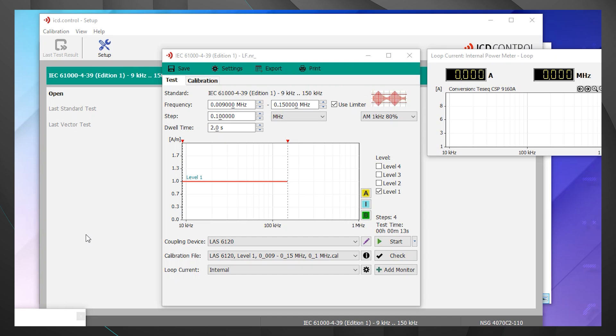Here is our test menu for IEC 61000-4-39. You will see we're currently in the test tab. We have our standard listed along the top, as well as the corresponding frequency range. Below that we have our step, next to that the modulation, and then below the step we have our dwell time. Just below the dwell time we have our graph. To the right of that, our test level. And then along the bottom we have our coupling device, calibration file, and loop current. Prior to running this test we have to run the calibration. So let's click on the calibration tab.